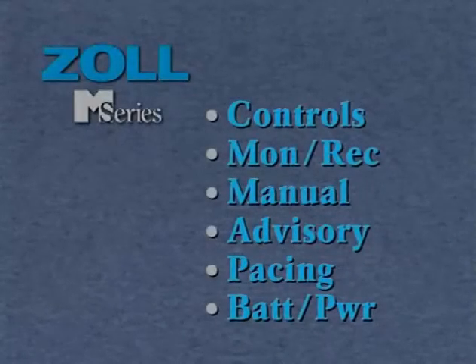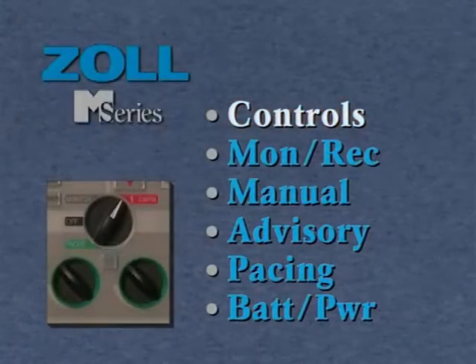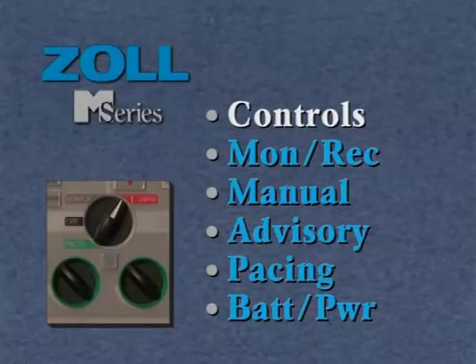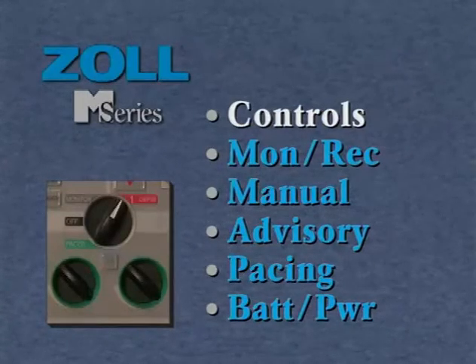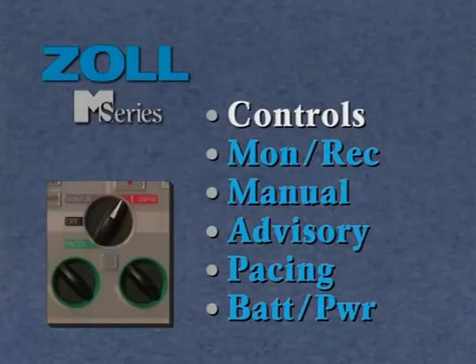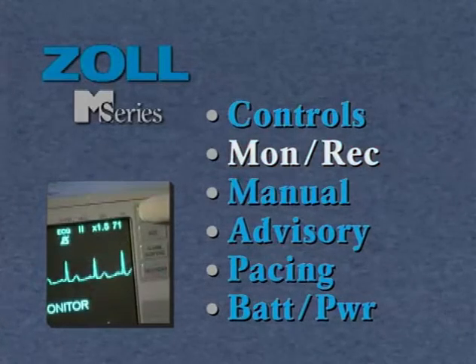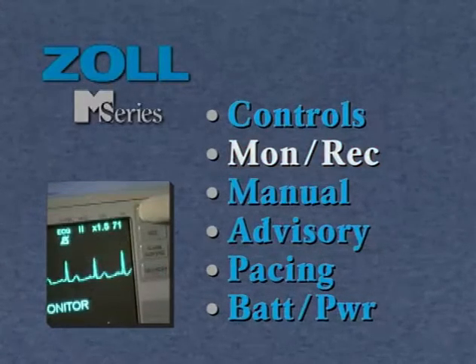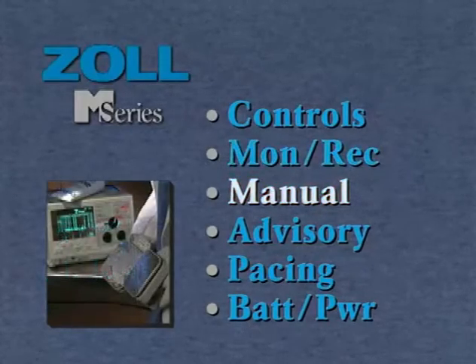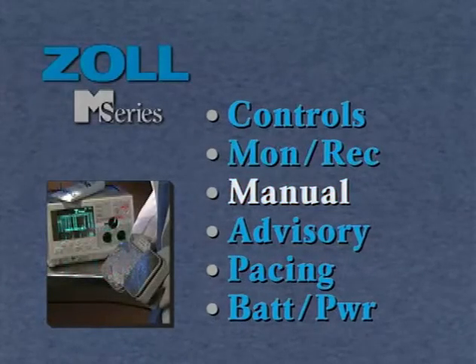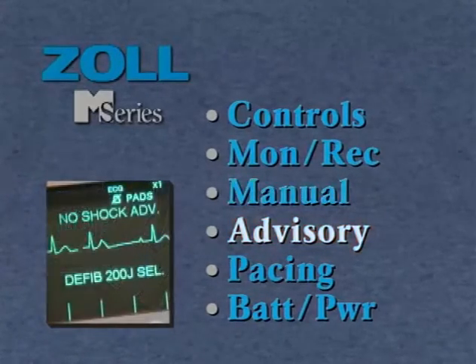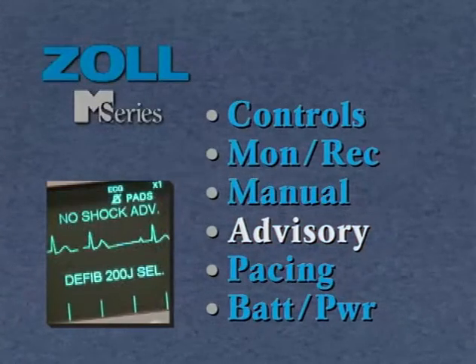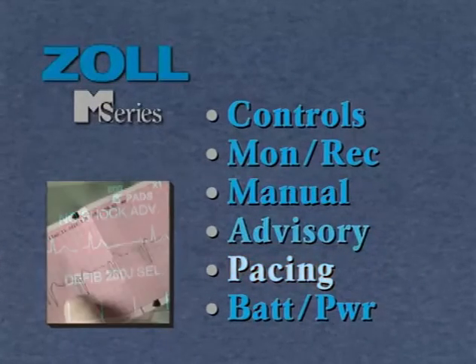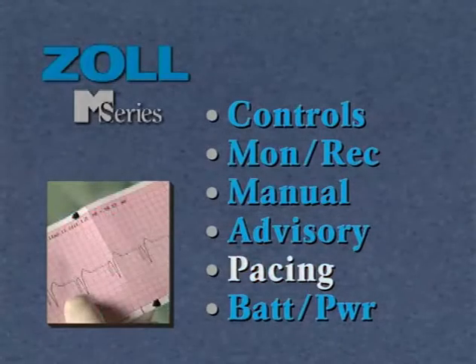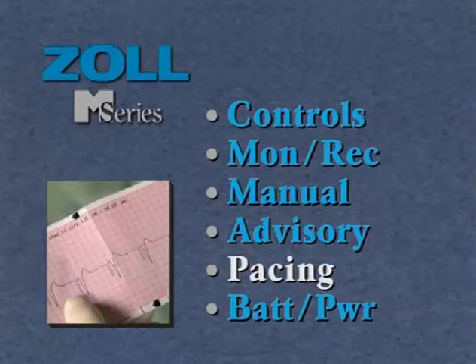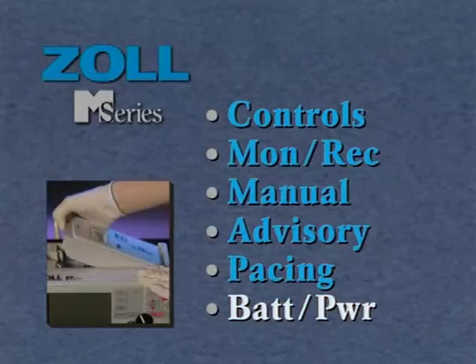The first section of the video, Standard Operating Controls, describes the basic operation of the ZOLL M Series. All operators should view this section. The monitoring and recording section should also be viewed by all operators. If you use the device for manual defibrillation, view this section. If you intend to use the advisory mode, view this section. To learn how to operate the device for pacing, view the pacing section. All operators should view the batteries and power section.